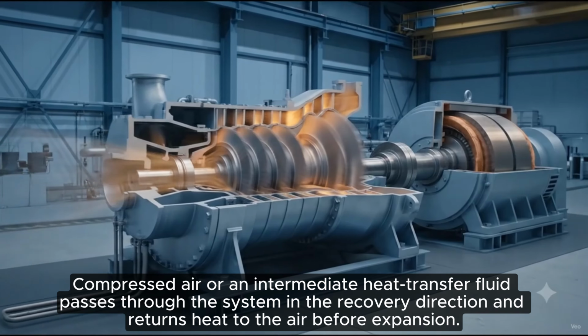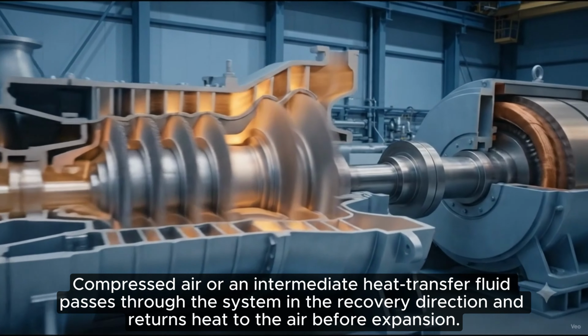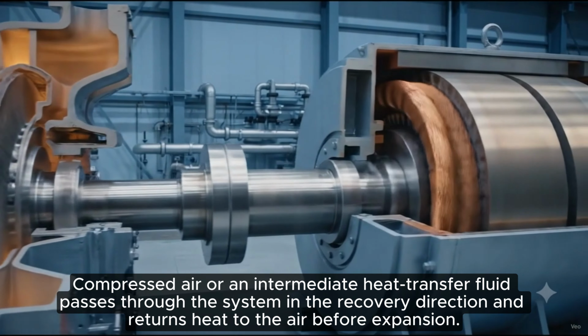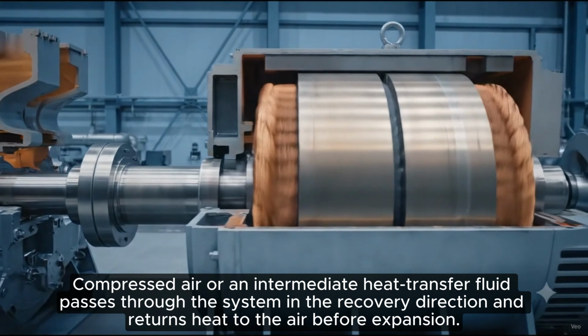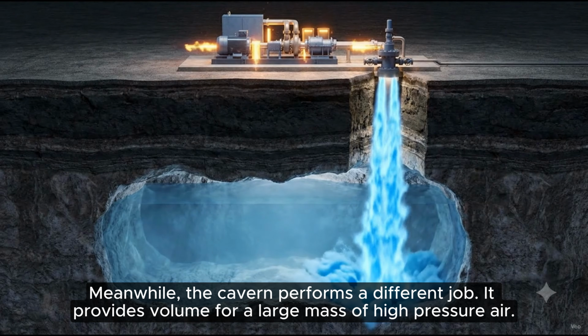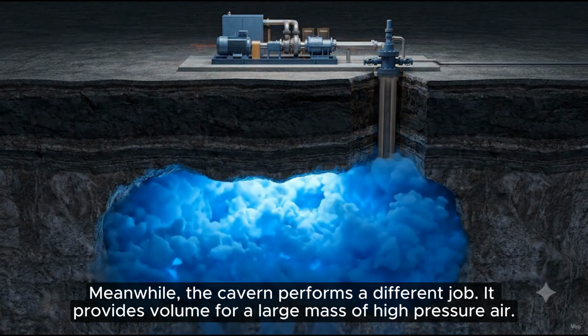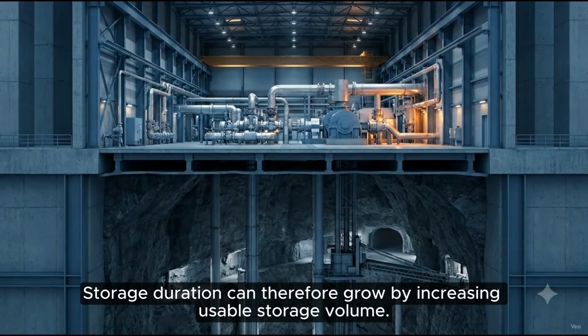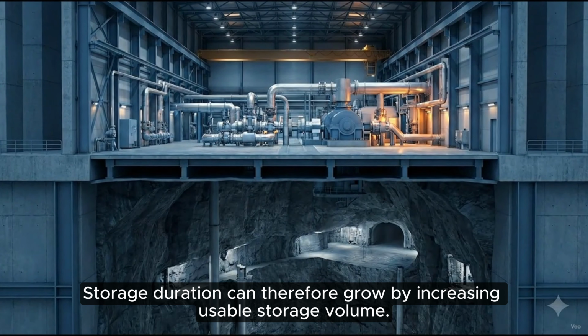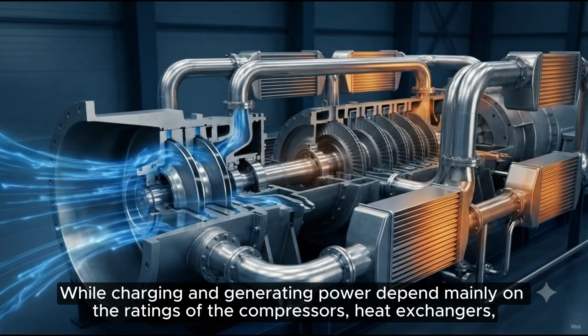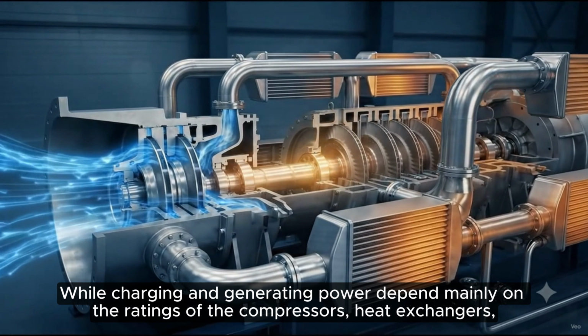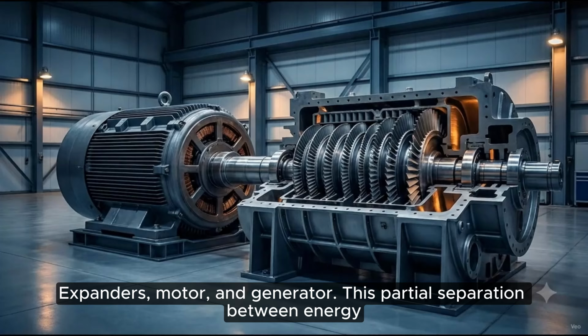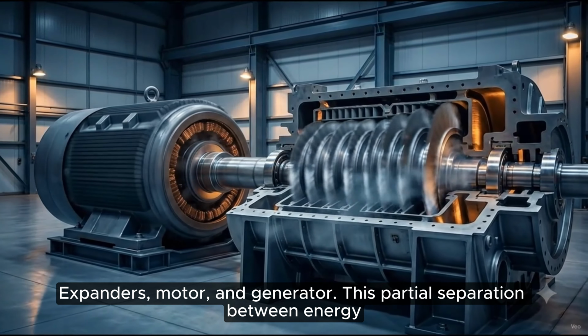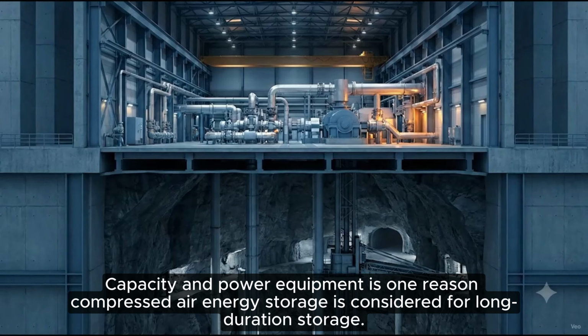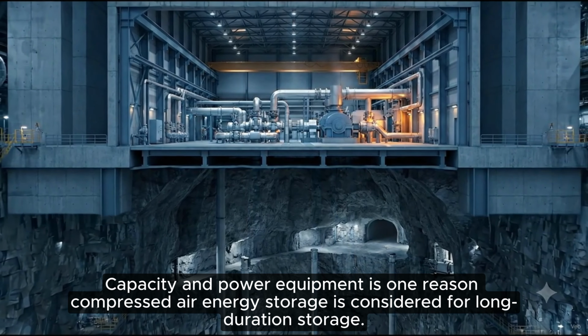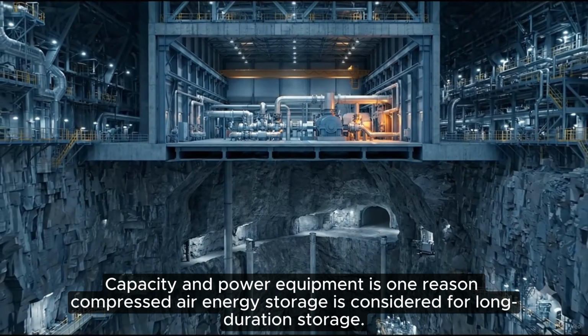During discharge, compressed air or an intermediate heat transfer fluid passes through the system in the recovery direction and returns heat to the air before expansion. Meanwhile, the cavern performs a different job. It provides volume for a large mass of high-pressure air. Storage duration can therefore grow by increasing usable storage volume, while charging and generating power depend mainly on the ratings of the compressors, heat exchangers, expanders, motor, and generator. This partial separation between energy capacity and power equipment is one reason compressed air energy storage is considered for long-duration storage.